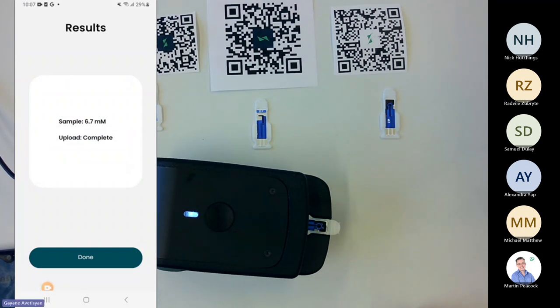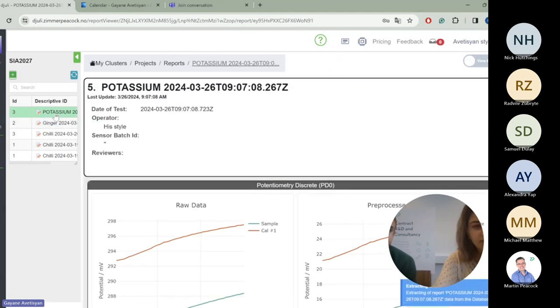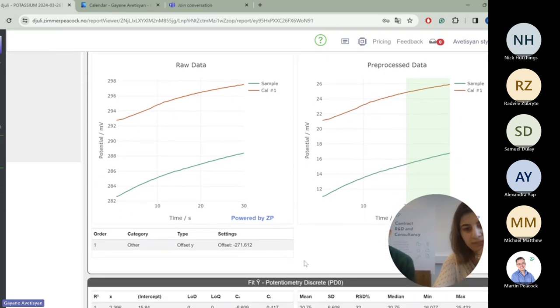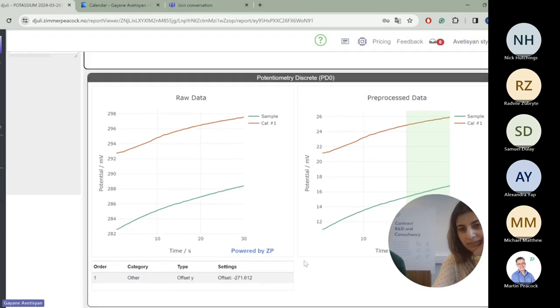The test is done. We can see the results on the app screen. If we want to dig into the actual data, we can do so in Djuli. After refreshing in the same cluster, we find the potassium test. We can see the raw data and pre-processed data — in this case running potentiometry, looking at the difference between the sample and our calibration solution. All of that is available in Djuli right after the test.